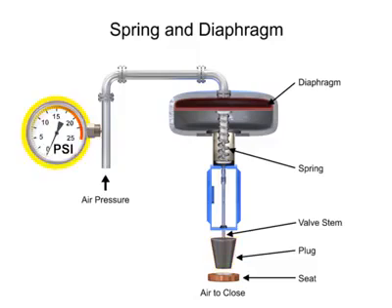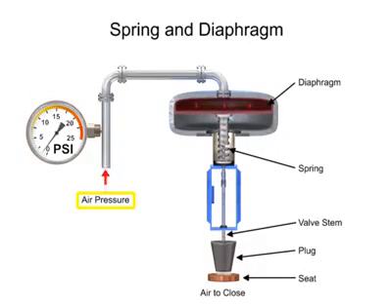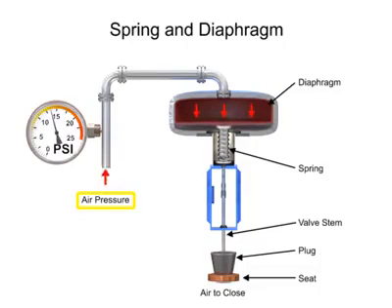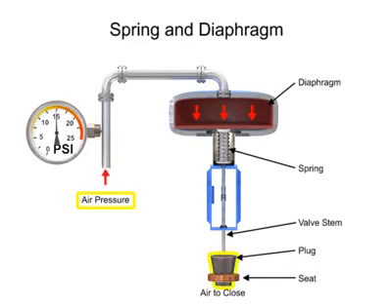A 15 psi pneumatic signal enters the housing at the top of the actuator. As pressure is exerted on the diaphragm, a downward force is applied against the spring which moves the restrictor. The diaphragm moves until it creates an equal but opposing force against the spring, at which time the motion stops as the plug meets the valve seat.